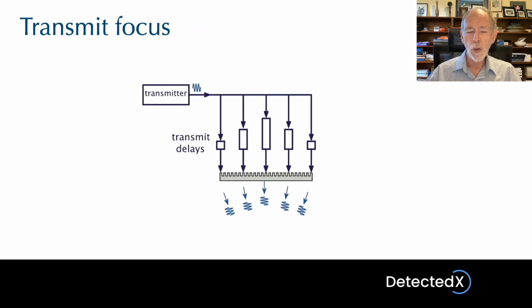So we saw before that the machine is going to have to transmit at different times from different parts of the transducer in order to get the pulses to arrive at the point of focus at the same time. And this, remember, is to correct for the fact that the pulses have to travel different distances from different parts of the transducer face. So here I'm showing the way the machine achieves this.